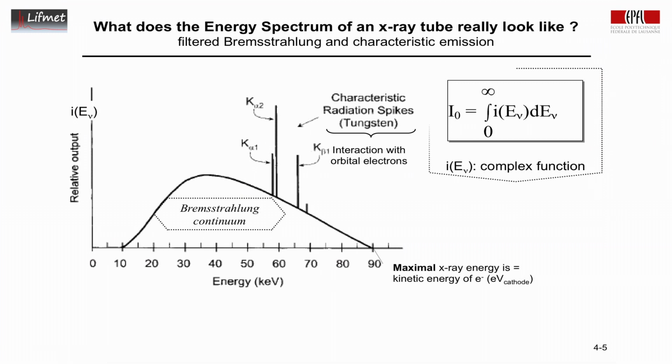The way this is done is to define an effective photon energy, E effective. It corresponds to the median energy of the photons that are seen by the subject. So the effective energy in this example would possibly be something like this, from the X-rays that are leaving the X-ray tube.